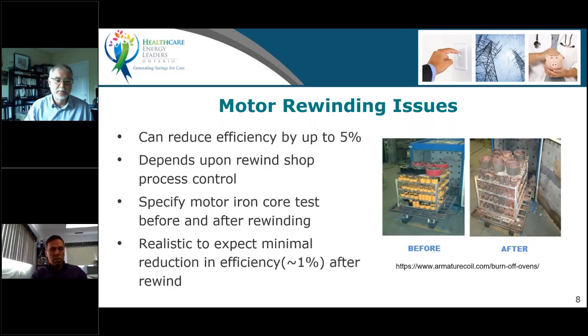So that's a very real thing. Works in pumps too. When it comes to rewinding motors, it does make sense, but we've got to be careful. The problem we have when we do a motor rewind is that the motor has to be baked out in order to remove all the varnish and the old wire. And when they bake it, if they don't control the temperature very closely, you can end up changing the properties of the iron in the motor, and that ends up reducing its efficiency in almost every case. A good motor shop can stick within 1%, but it could be as much as 5% per rewind, and it is somewhat cumulative as well.